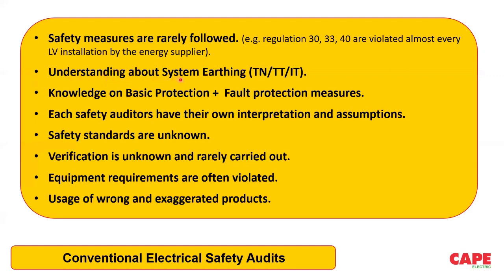Similarly, understanding about system earthing, TN, TT, IT. If you don't know what is TN, what is TT, and what is IT, you cannot do a verification. You cannot. Earthing is not about putting hundreds of earth pits. Earthing is about the best way of making one of these system earthings and ensuring that all the safety measures are made. So most of the time, the auditors are very rarely aware of TN, TT, and IT systems. I am making this statement because of my experience.